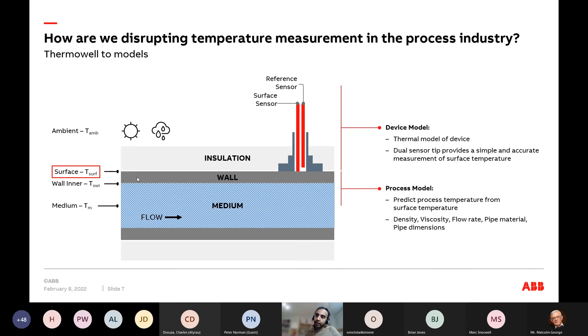In essence, we're measuring the ambient conditions right around the sensor and compensating for those effects. That allows us to both accurately and in a calibratable way measure the surface temperature of the pipe. Because the two sensors are very close together, you can capture the dynamics of the pipe's temperature change. This is one approach to get non-invasive temperature sensing — not using a thermowell, but actually turning that pipe into a sensor.